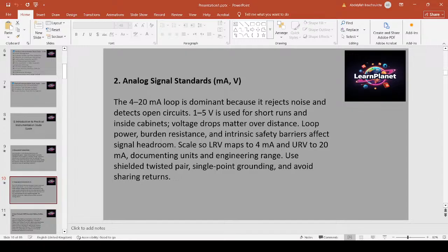Analog signal standards: milliamps, current or voltage. The 4-20 milliamp loop is dominant because it rejects noise and detects open circuits. 1-5 volt is used for short runs and inside cabinets. Voltage drop matters over distance.